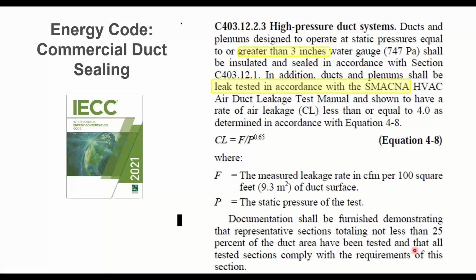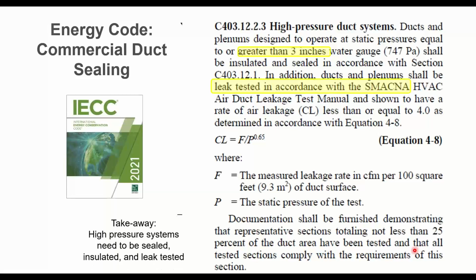So low pressure systems and medium, you just have to seal it. High pressure systems, you have to seal it and test it out. Because of that, people are being smarter and they're designing for things less than 3 inches, so they don't have to do this testing process. But once in a while, you have products where you have to do it.